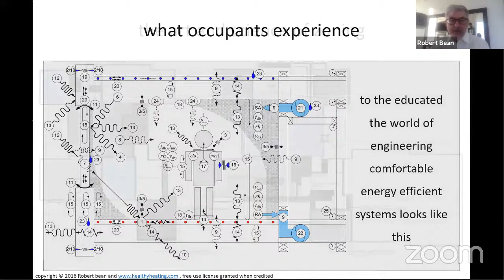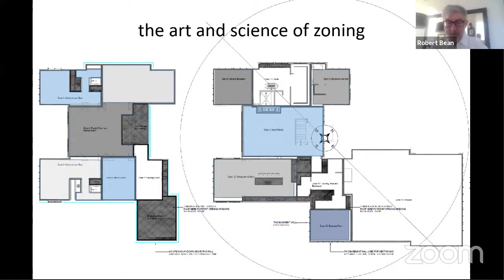So as designers and practitioners engineering systems, the first thing we must do is analyze the building itself and its footprint. We have to understand how the sun moves across the building surfaces, which changes how inside surface areas behave. We need to look at how the building's geometry relates to sun paths, and what the heating and cooling loads are in those spaces depending on architectural and enclosure design. When controlling these spaces, we try to avoid mixing zones with extreme loads versus those with conservative loads — zoning is incredibly important. We've addressed this in different documents, looking at spaces depending on whether they're for sleeping, working, or studying.